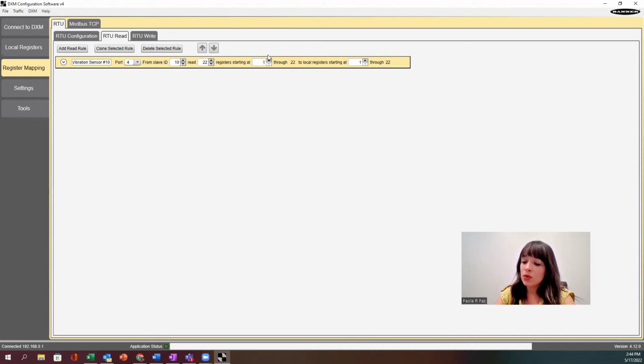So we said it was 45-01. Now the gotcha here is that you don't need to put that 4 ahead of it because we're already in the holding register. It automatically populates here to 5222. So we know we did it right, or we counted right anyway.